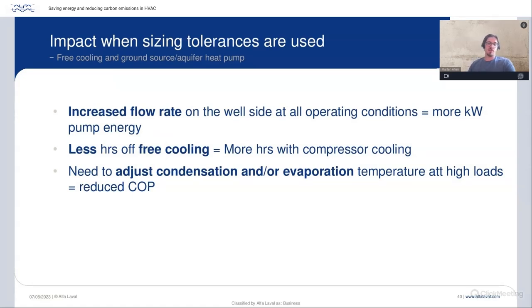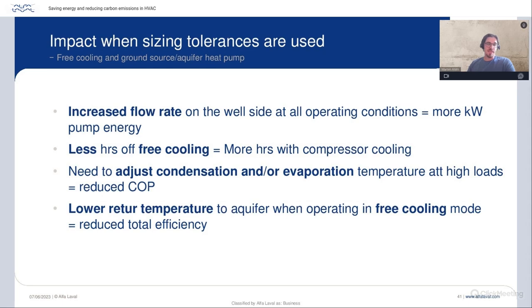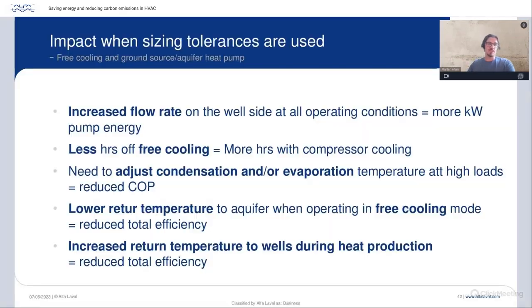So again, all of this goes in the same direction, that the energy efficiency goes down. If you work with free cooling, natural free cooling, and using the bedrock, as in this case, as a heat source as well, then you will always deliver, let's say, the wrong temperature. You will always have a deviation from what was specified to what you actually deliver to the bedrock. So if you run it for free cooling in the summer, you will store a lower temperature in the bedrock. And when you then turn it around to use it as a heating source, you will not have as high a temperature available. Again, all of this leads to an increased use of energy. So all in all, an undersized heat exchanger in this case doesn't perform, which generates higher operating cost.